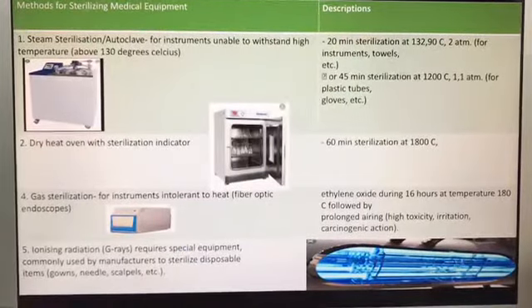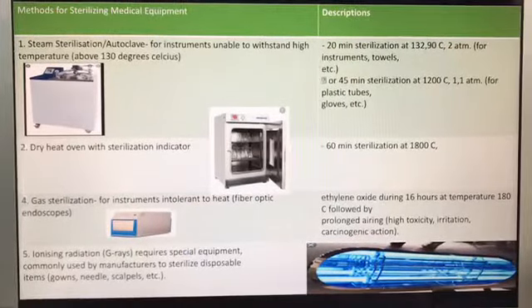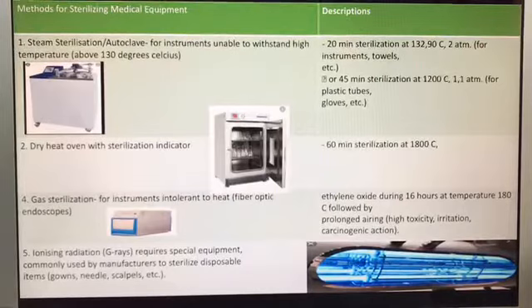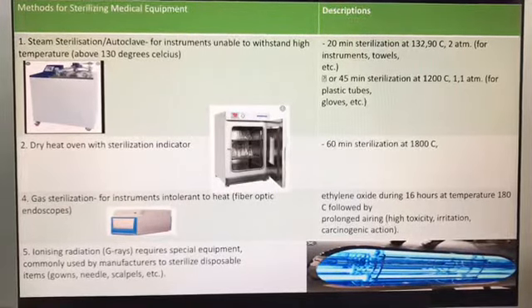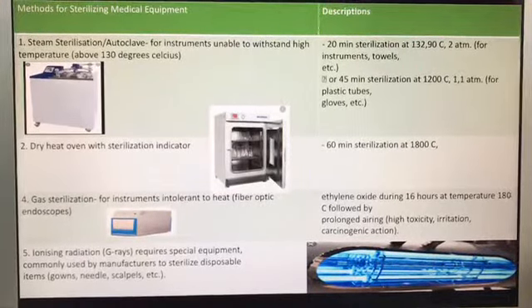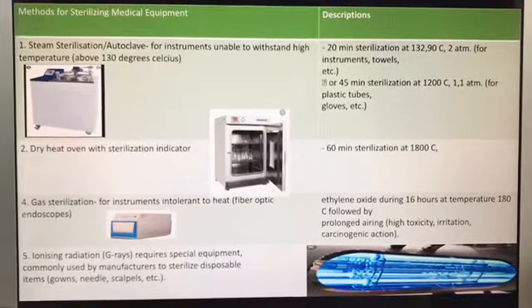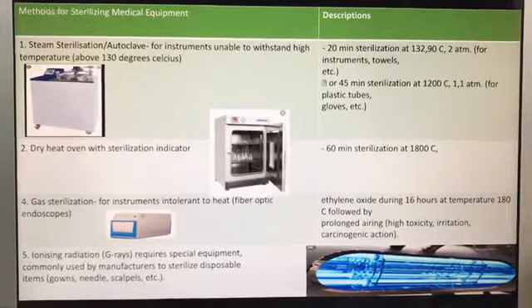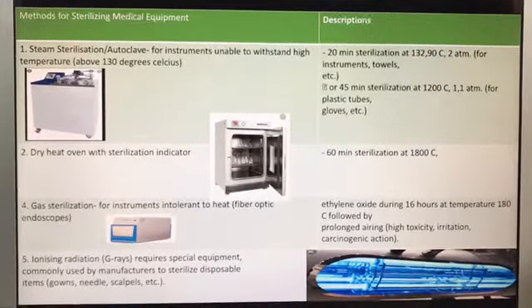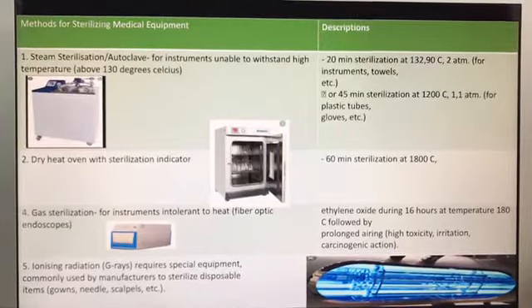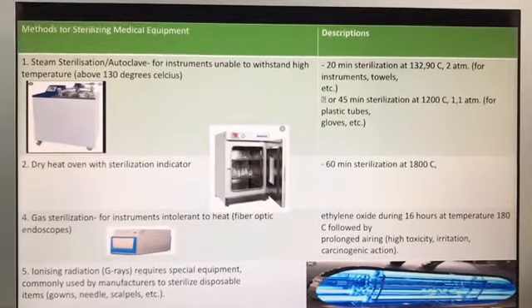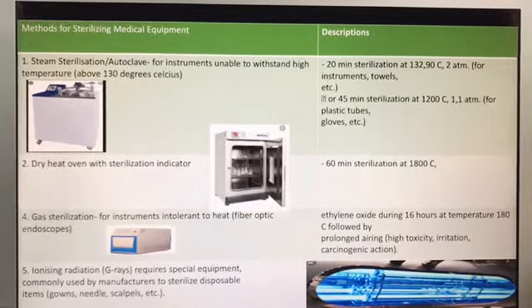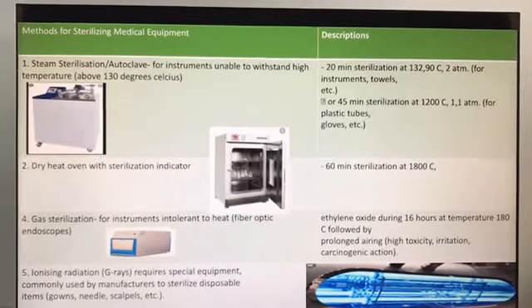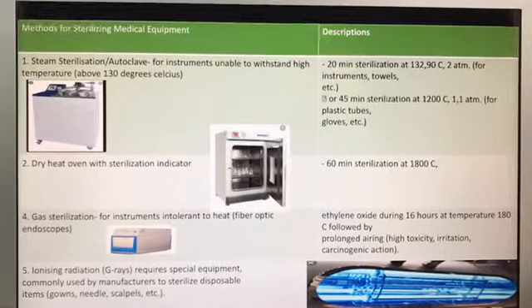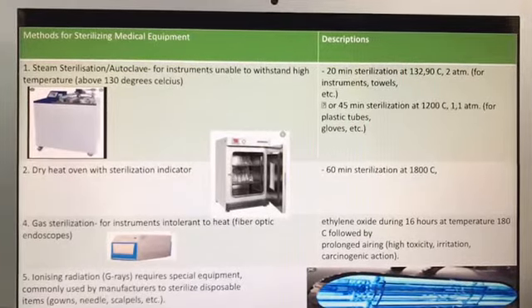Secondly, the dry heat oven with the sterilization indicator. When steam cannot penetrate an instrument or can destroy it, your next logical option is to use dry heat. Dry heat is a strong but very slow technique requiring high temperatures and time. Because of this, it is not very suitable for many materials, but it is still more reliable than various other options. Dry heat sterilization uses air at around 340 degrees Fahrenheit to kill microbial life. As you can see here, this shows what a dry heat oven looks like.